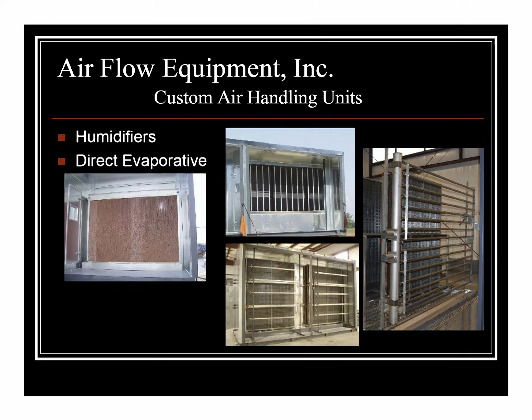I know when I design a unit, somebody calls me up and says, hey, can you lay out a unit? I like to send back, first a CAD drawing, fan curves, coil runs, but also this static sheet, just a breakdown and an accounting of all the static in the system. That gives us a tool to go through when we're designing that project up front and make sure all the static's going to be accounted for and that we're going to have enough air and enough pressure to make the job successful.